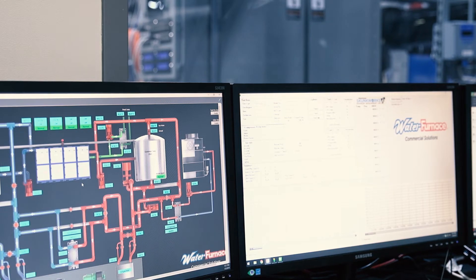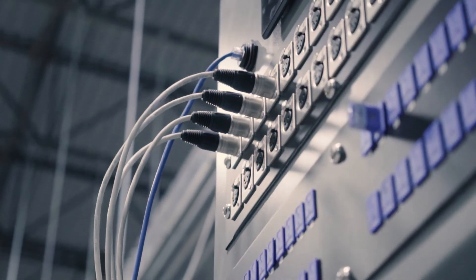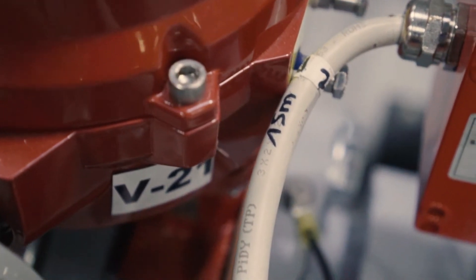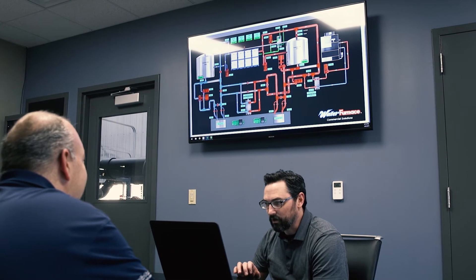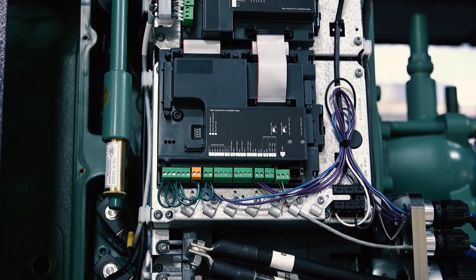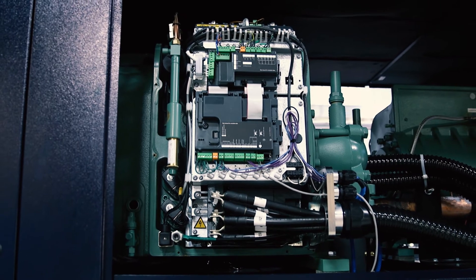The lab test computer is connected to the test chiller as well as the HydroLink supervisory control. All support equipment and temperature control is managed from the HydroLink supervisory. During testing, all highly accurate temperatures, flows, and power measurements are managed by our Water Furnace chiller lab software. Newer integrated permanent magnet variable speed compressor drives can be direct connected to the lab test station during development to ensure proper operation from the compressor manufacturer's perspective.